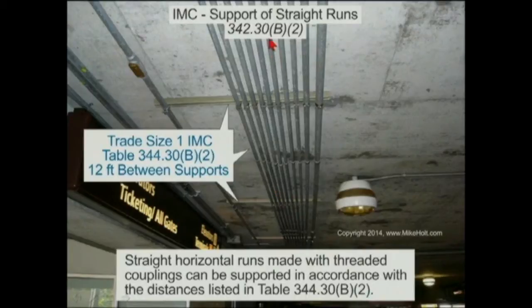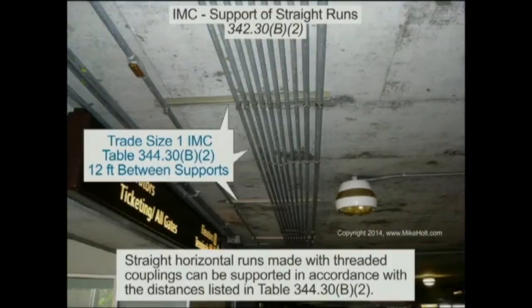Ryan, take a look at the rule. Is the rule saying that you have to support rigid conduit every 10 feet except as permitted in the table, or does the code just say you support it per the table? The distance between supports for straight runs of conduit shall be permitted in accordance with the table. So if we're not using threaded couplings, the rule is 10 feet.